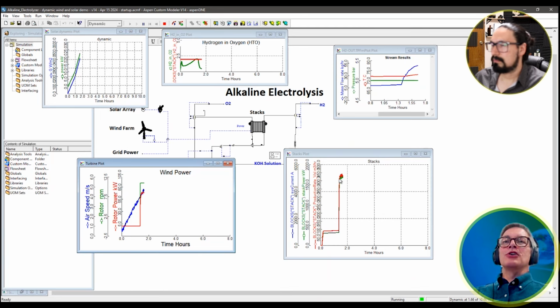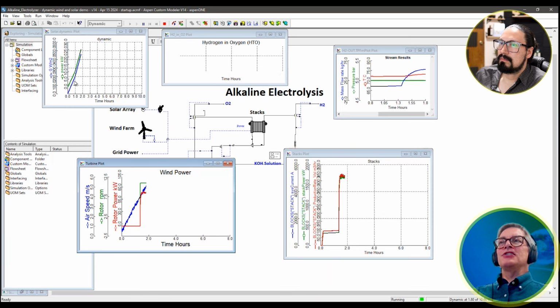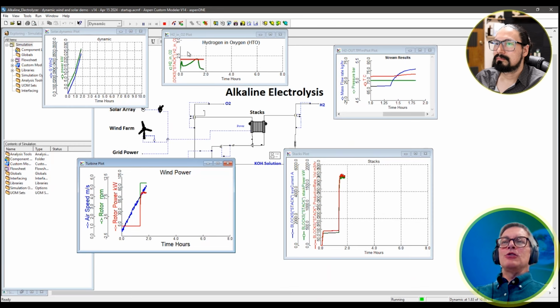So we got a bunch of noise here in the stack. And we can also see, towards the upper center, that around that time we got fairly close to our safety limit for the hydrogen and oxygen. Now, as we continue to increase the current density, the hydrogen came back down, so we're back in the safe zone.